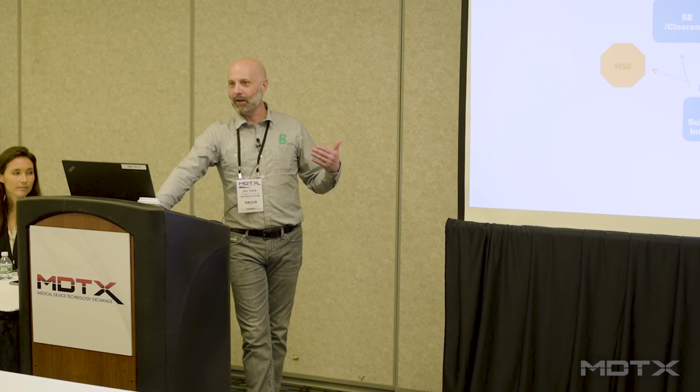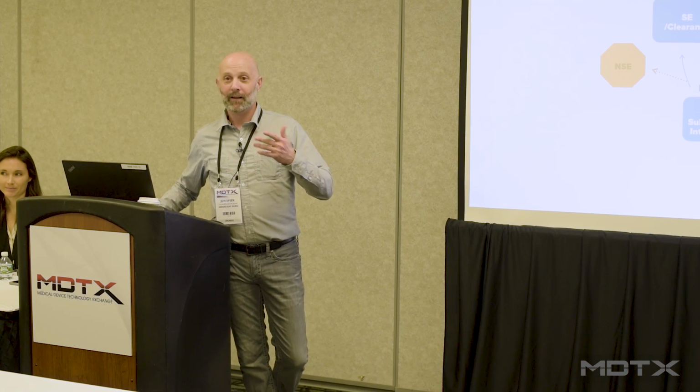And I've got a chart here. I'll show you a little bit on it, because I remember that I worked with a company a few years ago who had never been through the 510K process. And he's like, well, our device should take less than 90 days to get cleared from the 510K. And I kind of laughed at him, and he didn't like that. Because it's rare that a 510K takes 90 days or less from the moment you submit it to the moment you get cleared. How many of you have had a 510K take 90 days or less? Traditional. All right. You've had some experience as well. But this is part of knowing the process, the structure, the format, and knowing enough about the art where you can set yourself up for success.